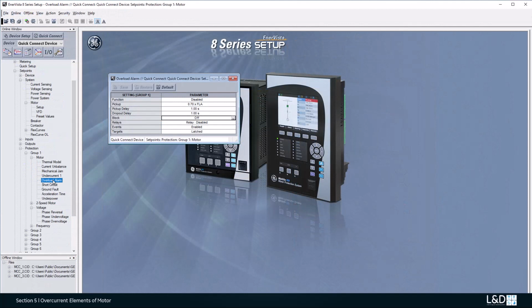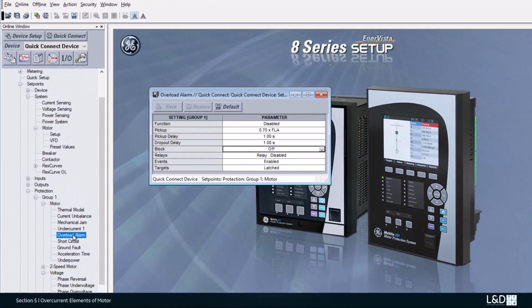The overload alarm is used to alarm on abnormal load increases that can indicate problems with the process. The alarm is enabled only after the acceleration stage is complete and the motor has entered the running or overload stage. Once enabled, the alarm is generated when the biased motor load current exceeds the pickup setting for the time delay specified by the pickup delay setting.